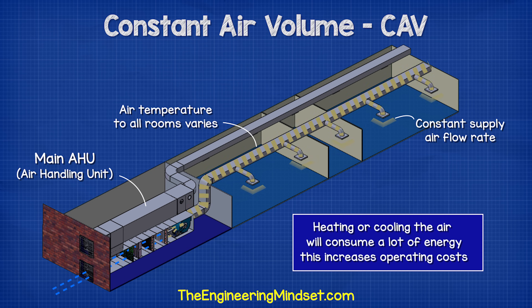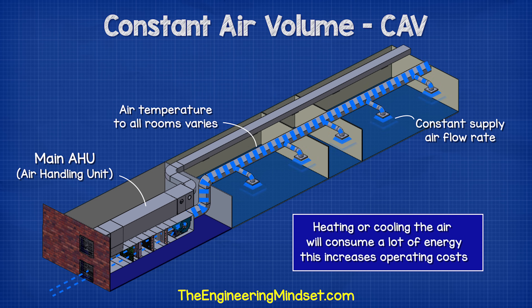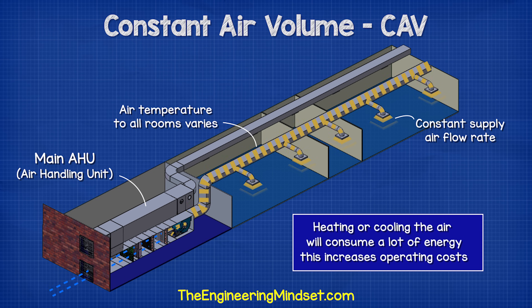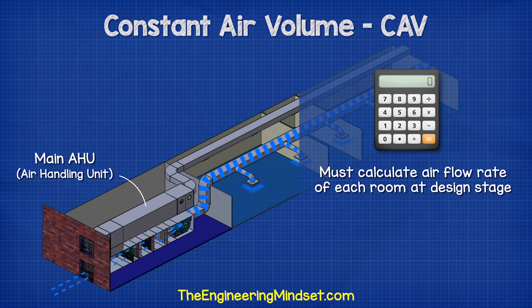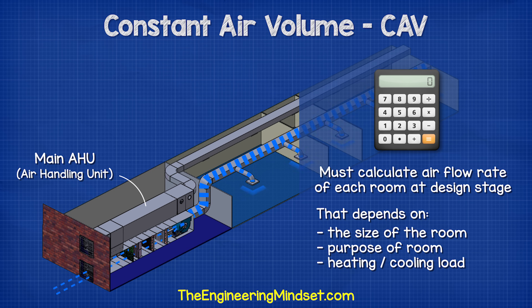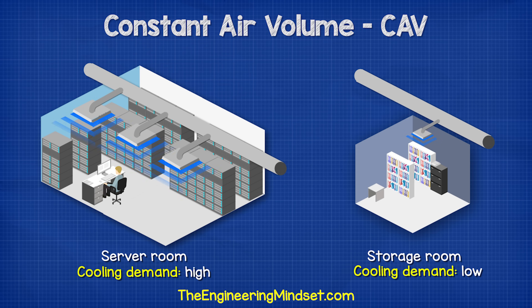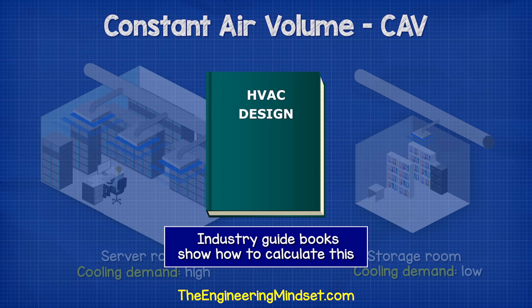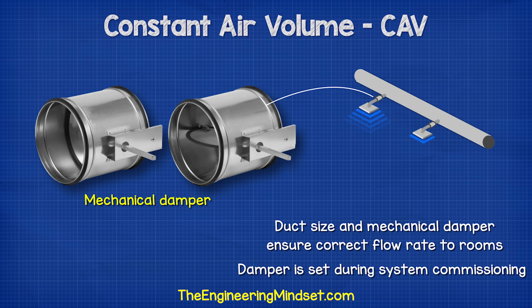Heating or cooling the air does consume a lot of energy and this increases the operating costs of the building. The volume flow rate of the entire system and therefore each room is kept constant. We have to calculate how much air each room will receive during the design phase. That depends on the size of the room as well as the purpose or what's happening inside each room. For example, a server room is going to require far more cooling than just a storeroom. There are industry guides available which will tell you how to calculate this. Each branch has a mechanical damper which is manually adjusted during commissioning to ensure the correct air flow rate as per design.